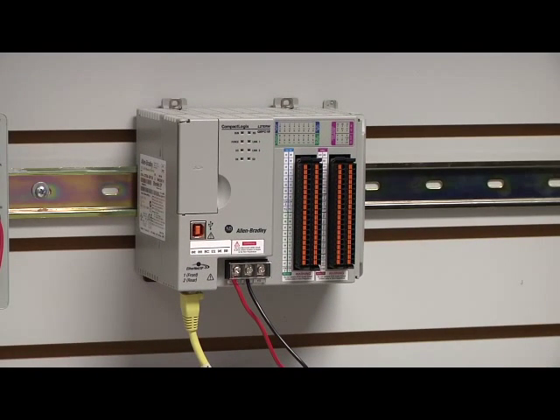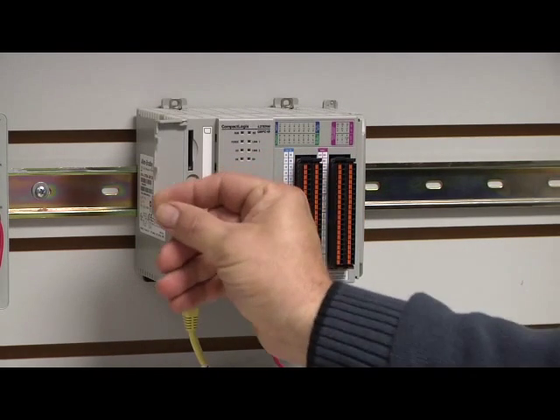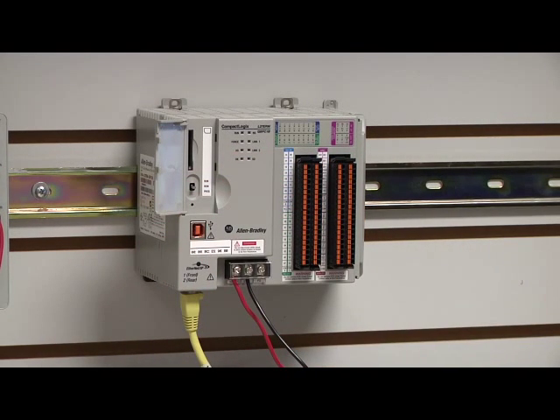This is our CompactLogix L27ERM. Under the front door is an SD card slot. When the program is configured in RSLogix 5000, the program can be configured to automatically upload upon power up. That's what we've done with this program.